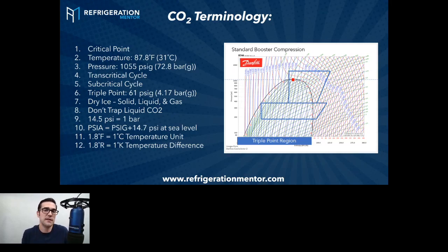As well, there are some other characteristics of CO2 as a refrigerant versus a synthetic or an HFC refrigerant. There's something called the triple point. The triple point is where you have liquid, vapor, and solid, and what that causes is something called dry ice. So if you try to charge a system that you just evacuated down below 300 microns, or 0.3 torr, that means you can't just add liquid at that point.